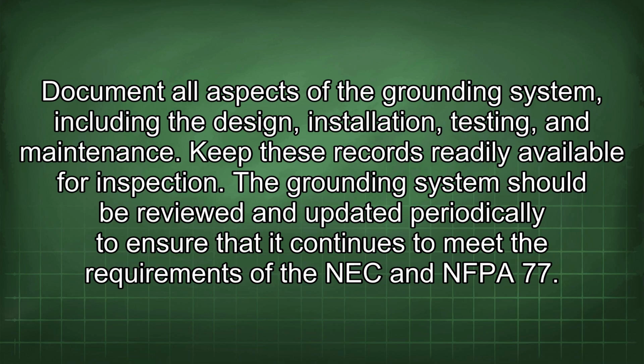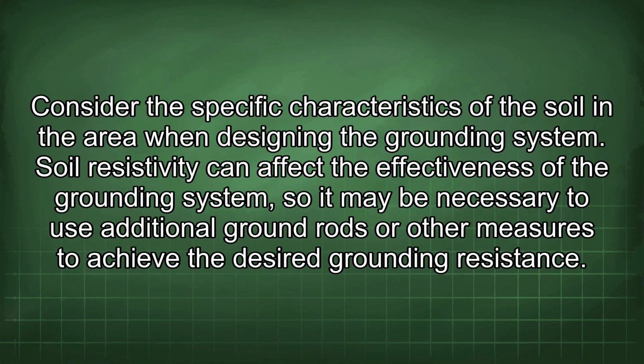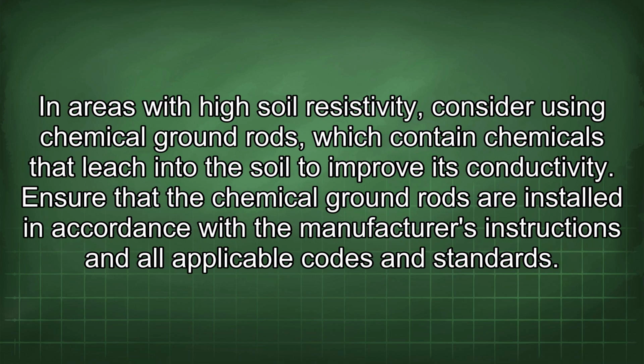NEC and NFPA 77. Consider the specific characteristics of the soil in the area when designing the grounding system. Soil resistivity can affect the effectiveness of the grounding system, so it may be necessary to use additional ground rods or other measures to achieve the desired grounding resistance. In areas with high soil resistivity, consider using chemical ground rods, which contain chemicals that leach into the soil to improve its conductivity.